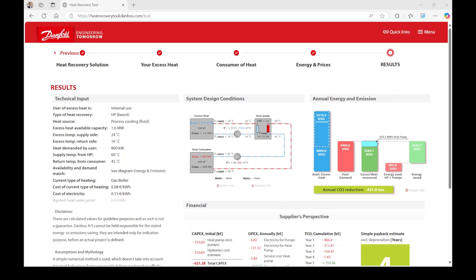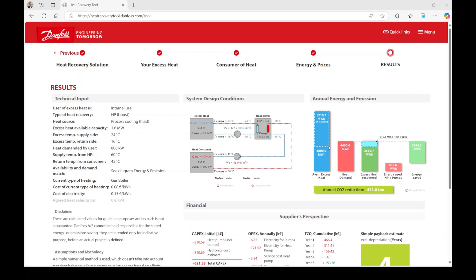If a heat pump is part of your heat recovery project, the compressor power will contribute additional heat, which is highlighted in the light blue box. If there is more excess heat available than your demand requires, a portion of this excess heat will remain unrecovered. This additional unrecovered heat can be utilized, for example, by supplying it to a district heating network.